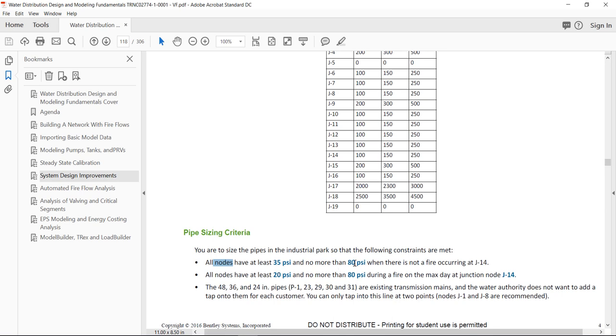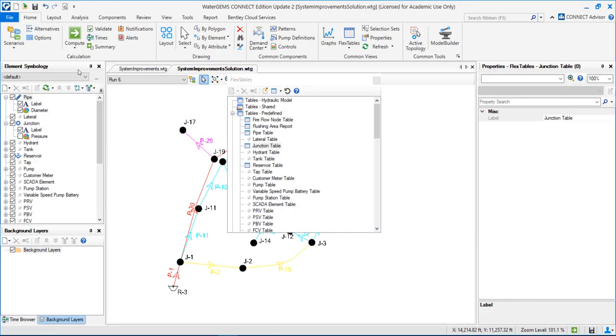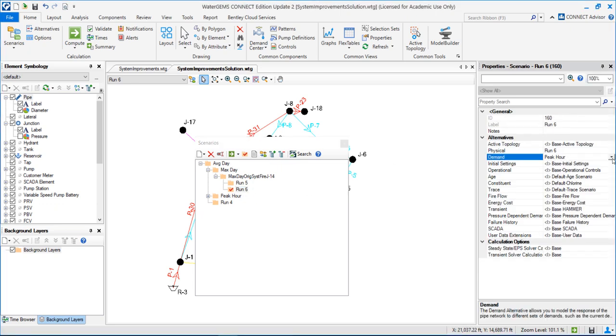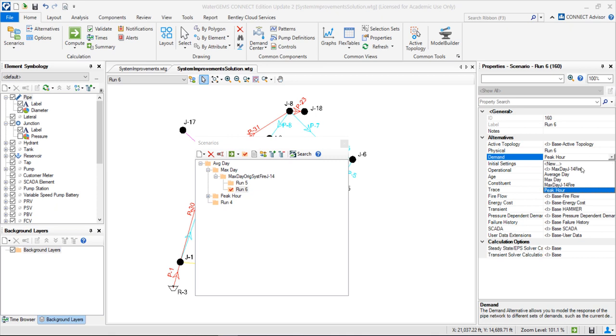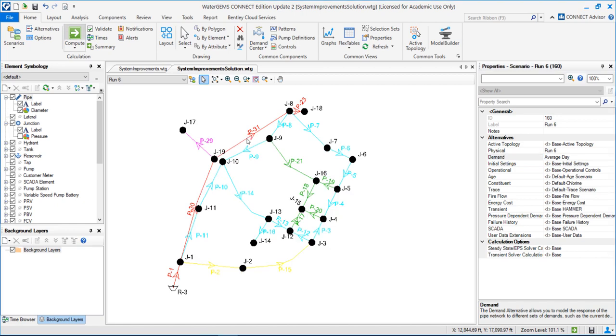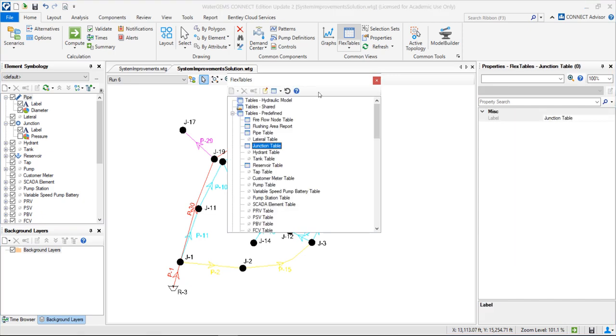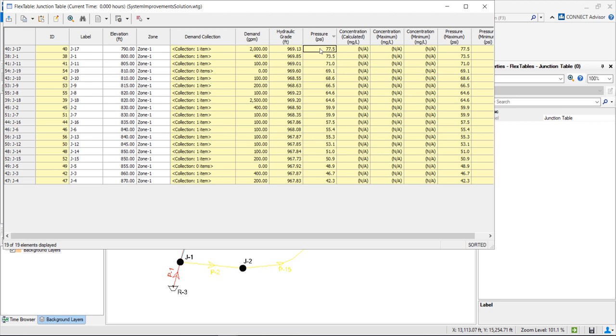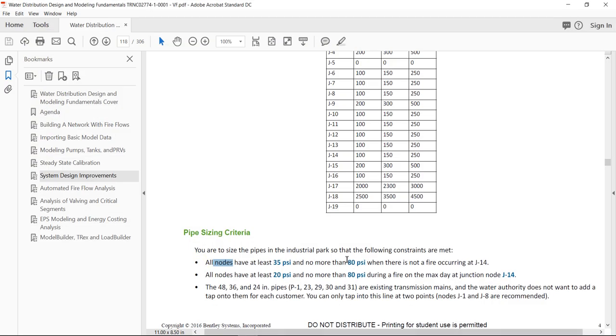Now we have to assure that all nodes have pressures lower than 80 psi. We should verify this for lower demands. So we go to scenario number 6 and choose the demand alternative for lower demands — in this case, average day demands. We compute, then go to the flex tables, the junction table, sort descending, and see that the node with the highest pressure is 77 psi, which is lower than 80 psi. So we have met these two criteria.